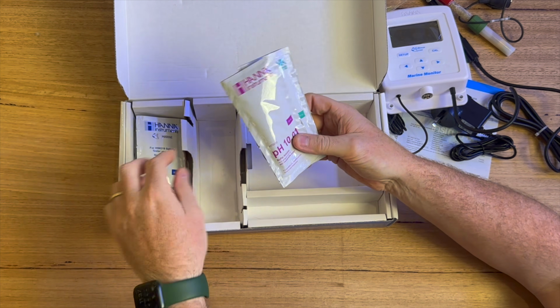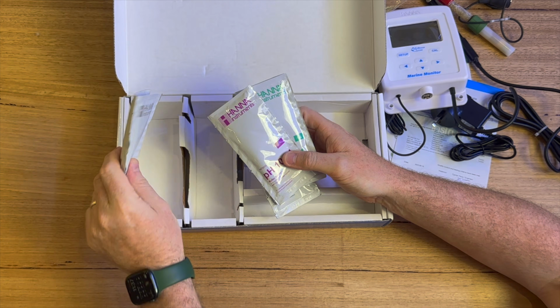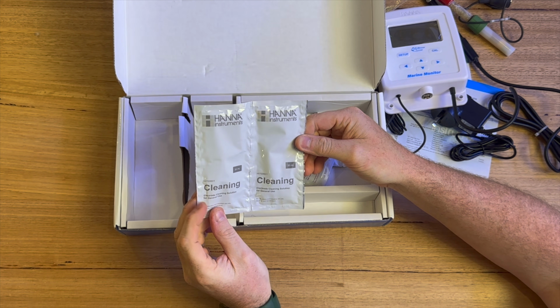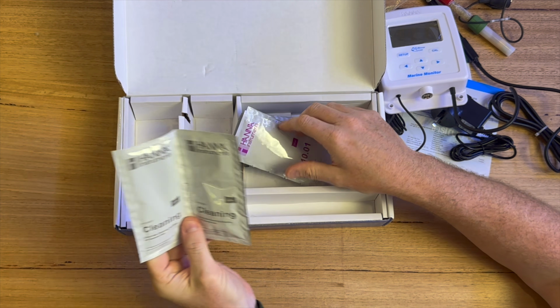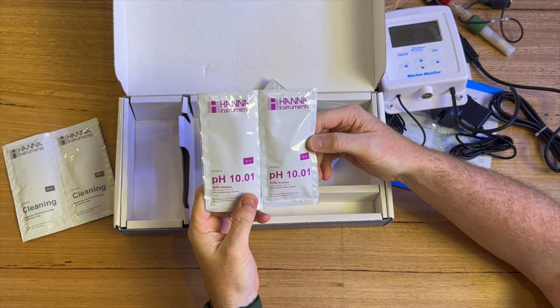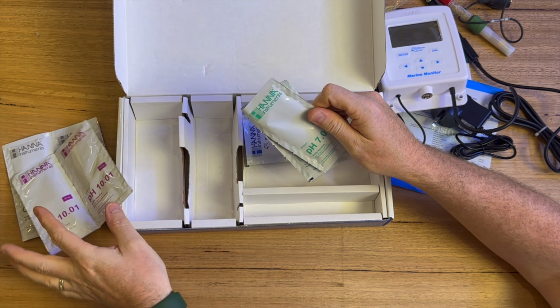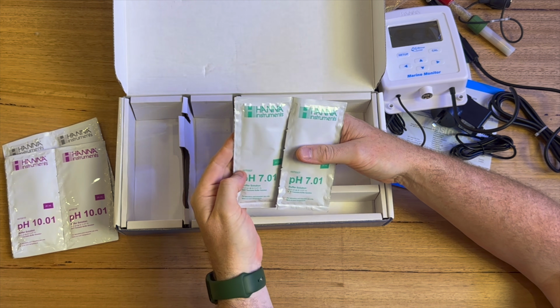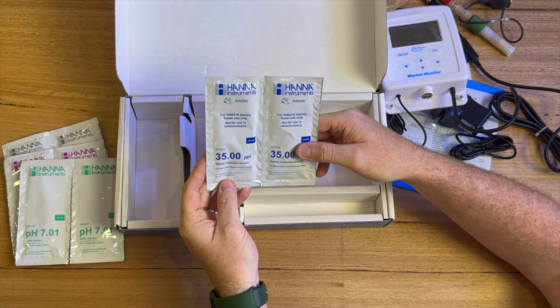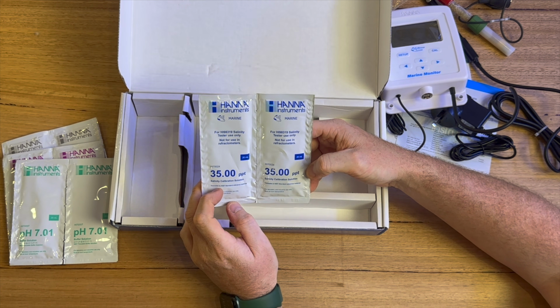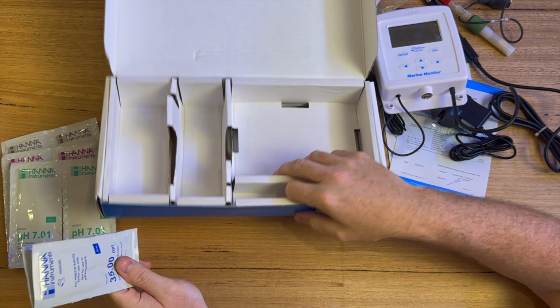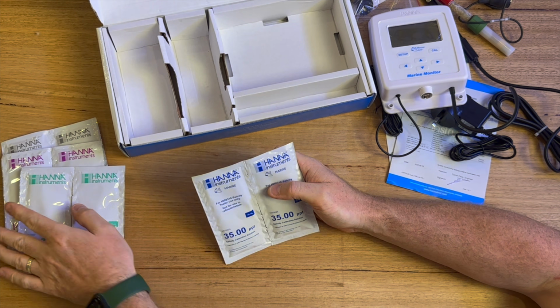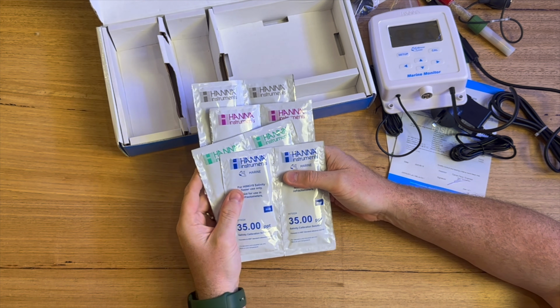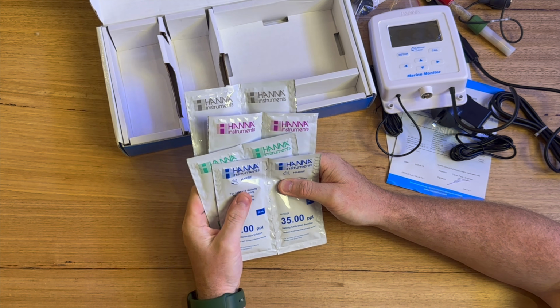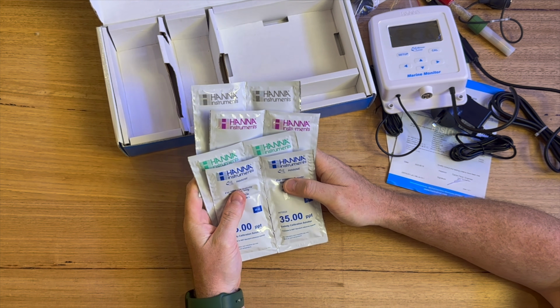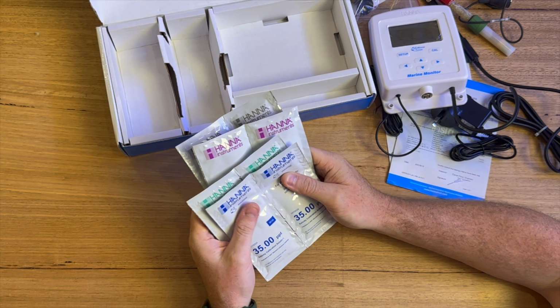And then we get a pretty solid assortment of calibration and cleaning fluids here. So we get 2 sachets of probe cleaning solution, which is always good. We get 2 sachets of pH 10.01. We get 2 sachets of pH 7.01. We get 2 sachets of conductivity 35 parts per 1,000 solution, and that's everything. So you get a good assortment of calibration and cleaning packets, which these are all available separately. You can get these from anywhere that sells the Hanna range. You can pick up their calibration and cleaning solutions, which is good.